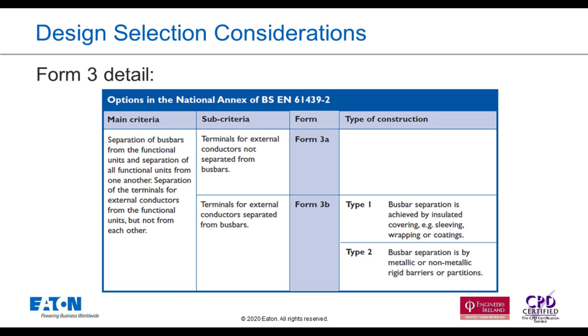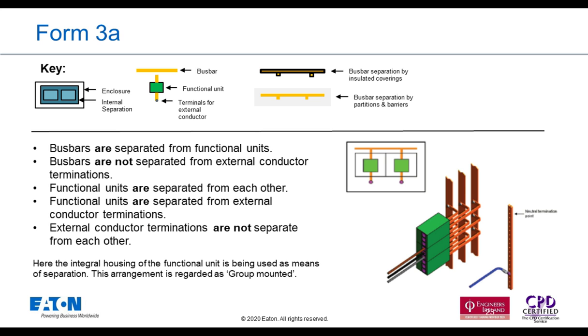So moving on to Form 3 here. The criteria here is that the main bus bar is separated from the functional unit. Each functional unit is separated from each other, and the cable terminals are separated from the functional unit. You've got 2 sub-criteria, 3A. In 3A, the cable terminals don't have to be separated from the main bus bar, and in 3B, the cable terminals do need to be separated. And again, Type 1 and Type 2, we'll have a look at these on the next slides.